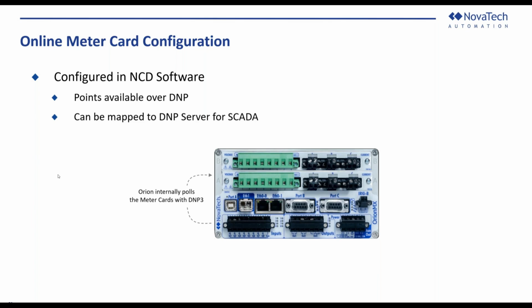Thanks for that. So now we've looked at the various applications for OrionMX. I'm going to just go through how to configure the meter card in NCD. So the online meter configuration is, Orion internally polls the meter card with DNP. The points are available for DNP and can be mapped to a DNP server for SCADA monitoring and control purposes. Let's take a look how that can be done. It's still the same software, no additional software is required.